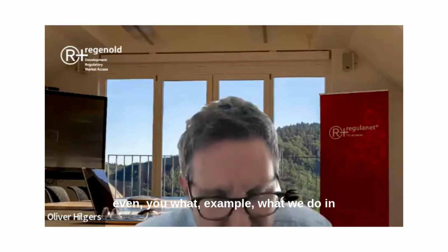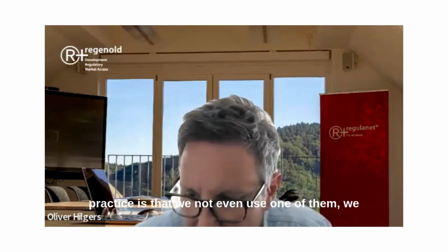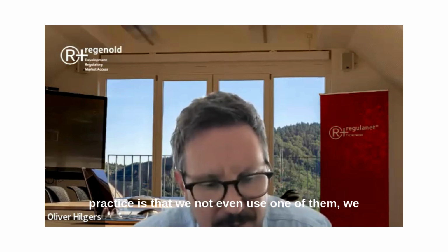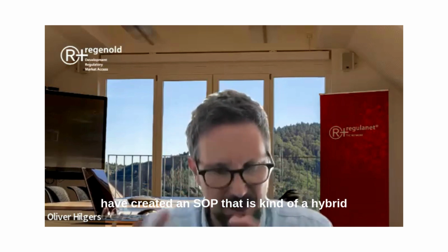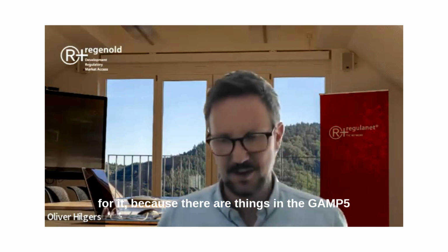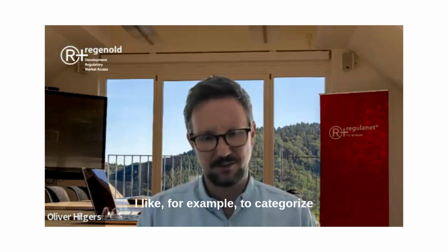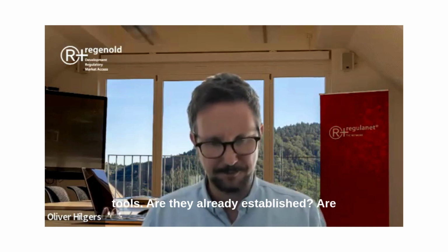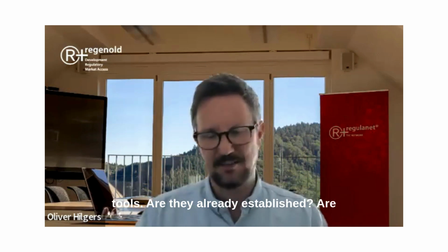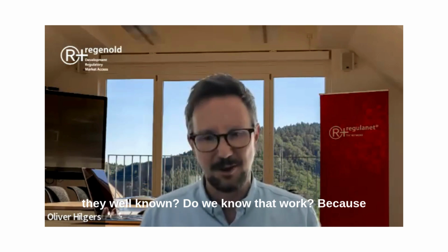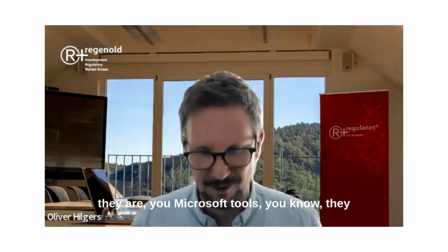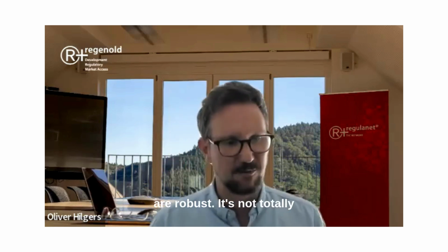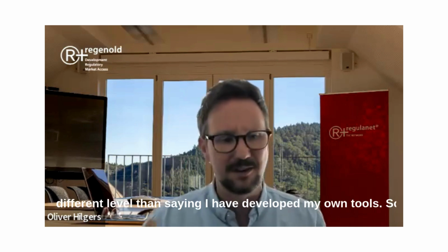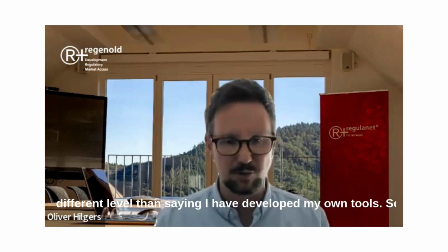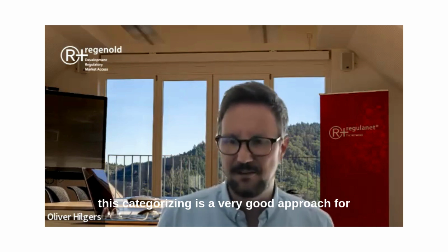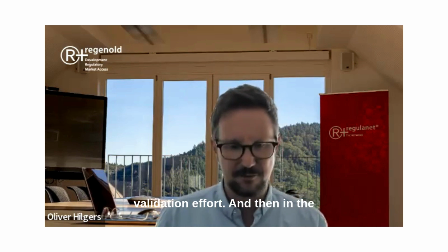And even, for example, what we do in practice is that we do not even use one of them. We have created an SOP that is kind of a hybrid, because there are things in GAMP 5 I like, for example, to categorize tools. Are they already established? Are they well known? Do you know that they work because they are like Microsoft tools? You know they are robust. It's not the same level as saying I have developed my own tool. So this categorizing is a very good approach for validation effort.